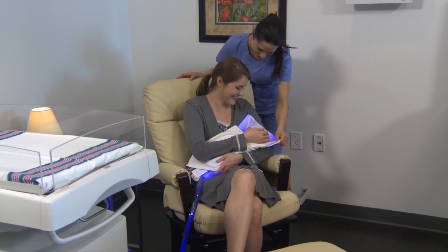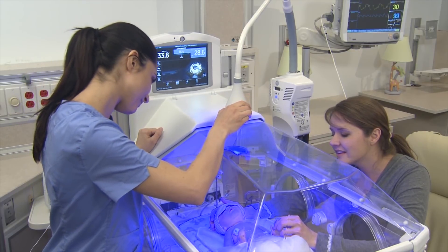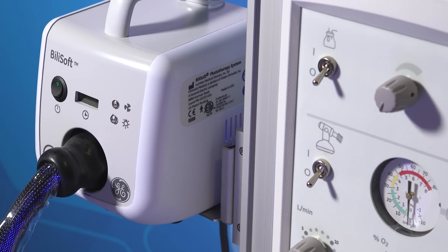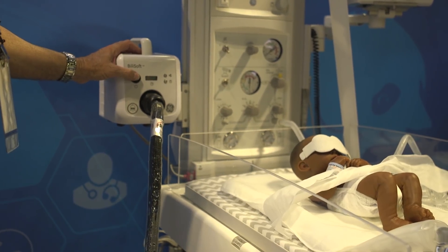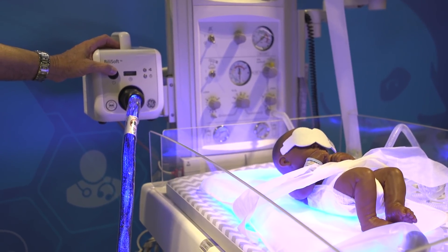The trend of couplet care or rooming-in is going strong. Many hospitals have shuttered their traditional nurseries and are now keeping babies mostly with mom. But instead of sending the baby to the nursery for phototherapy, how about keeping the baby close to mom. With the BiliSoft phototherapy system, mom can hold and feed the baby during phototherapy sessions, providing intensive phototherapy as recommended by AAP guidelines.